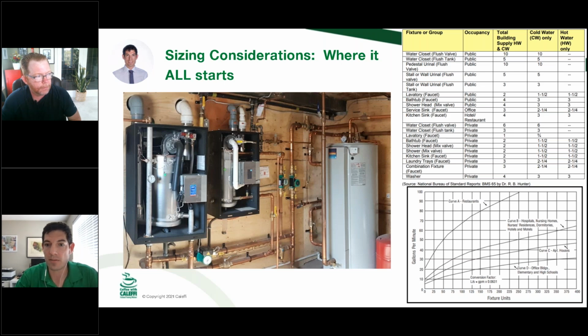It's going to depend on the type of use case and things like that. But as an example, if you were going to do a 10-plex of just regular sized condos, using these calculations, you might come up with a design peak flow of 50 GPM. And then with the more modern calculators, like we'll show on the next slide, it might be 19. So it's really taking a deeper look at which calculator you're using, because you might end up with a much better system, smaller pipe sizes, smaller components, less expensive, and more importantly, better performance instead of having something that's maybe 2 times oversized for what the actual use case is, incorporating some modern feedback like the IAPMO group is doing with their calculator.